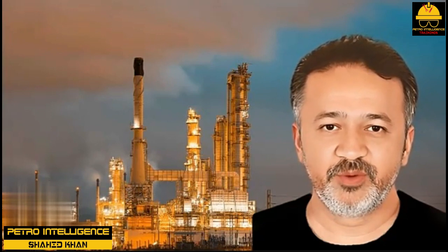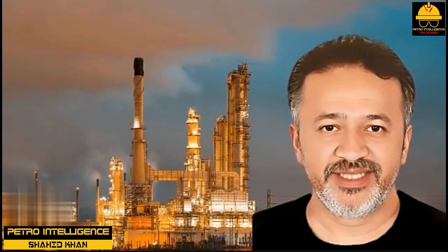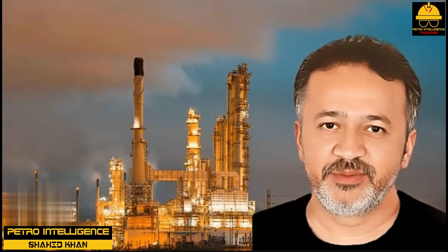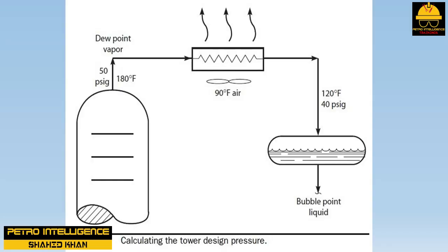Selecting an Optimum Tower Pressure. The process design engineer selects the tower design operating pressure as follows. First, determines the maximum cooling water or ambient air temperature that is typically expected on a hot summer day in the locale where the plant is to be built. Second, calculates the condenser outlet or reflux drum temperature that would result from the above water or air temperature. Third, the designer calculates the pressure in the reflux drum, assuming that the condensed liquid is at its bubble point. Adding 5 or 10 PSIG to this pressure for pressure loss in the overhead condenser and associated piping, the designer then determines the tower top pressure.